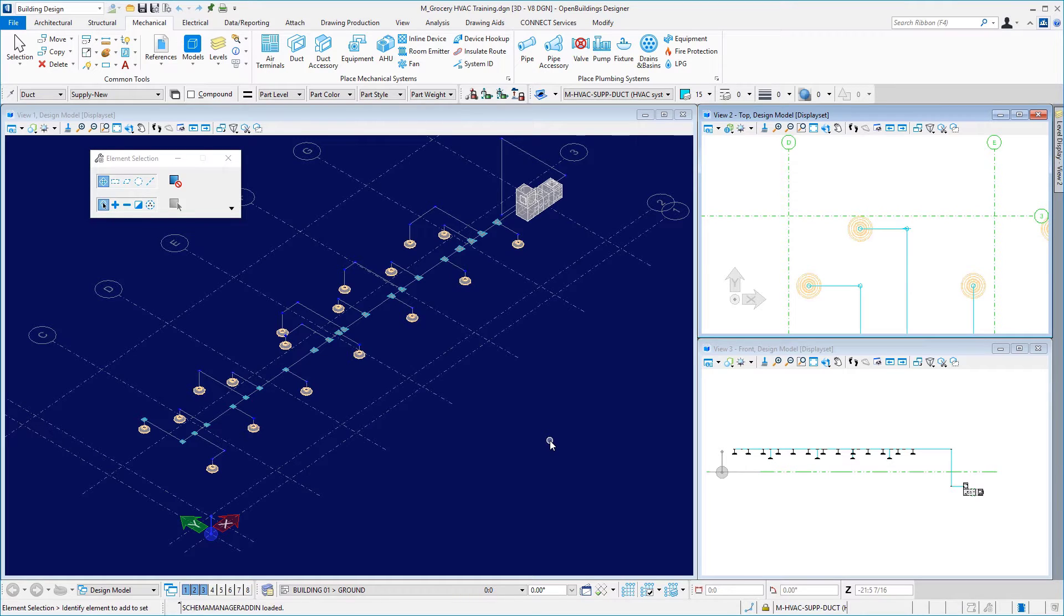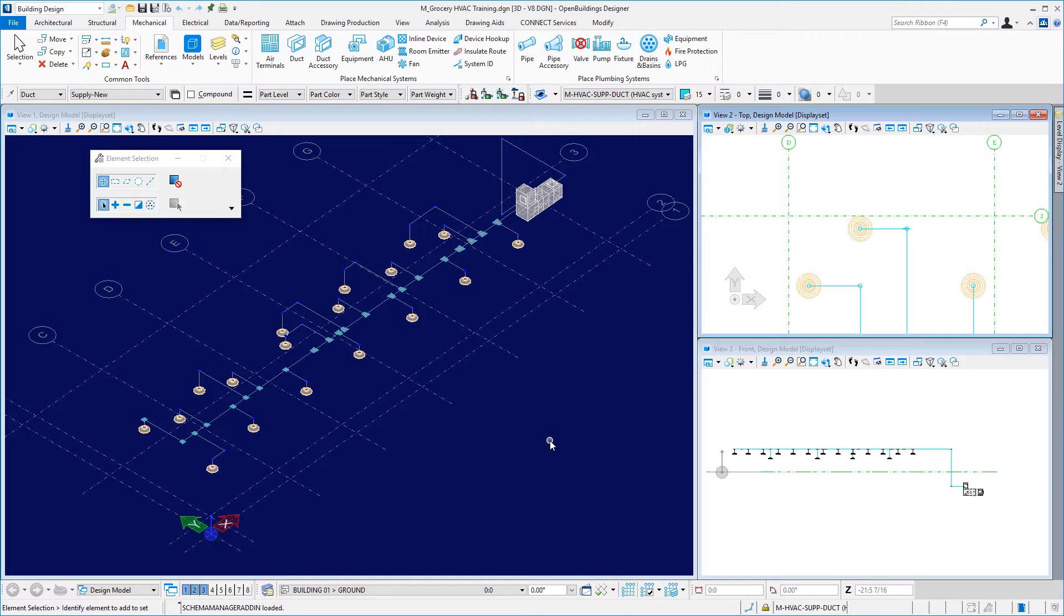The duct system sizing utility is used to map a system and perform sizing algorithms, resize and rebuild the system, and edit the system to coordinate the layout. The analysis can continue and be repeated throughout the design process to produce completed systems. The utility creates part, fan sizing, and pressure drop outlets and sizes the system using either ASHRAE or CIBSE equal friction methods, and it utilizes ASHRAE or CIBSE duct fitting databases.